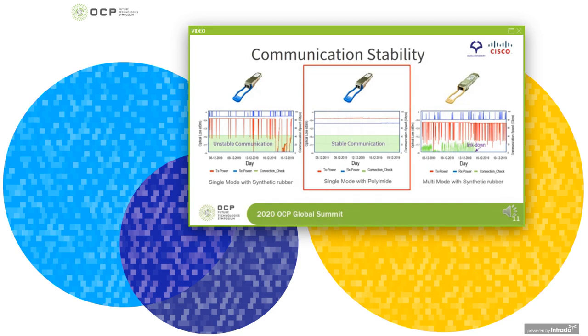So as long as the wiring surface of the 40 gigabit per second module is coated with polyimide, liquid immersion is effective with optical communication devices such as core switches and routers, as well as servers. In other words, servers and switches, which are the hotspots in the data centers and communication machine rooms, can all be immersed and cooled without intense air conditioning, resulting in dramatic energy savings.